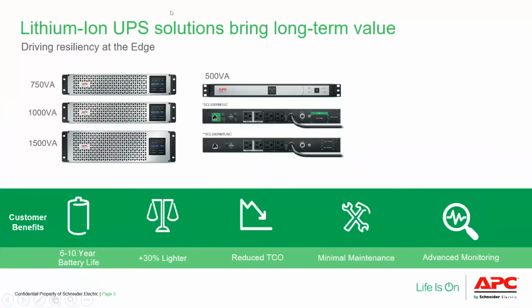From a total cost of ownership perspective, lithium-ion is a great solution for reducing total cost of ownership when paired against lead acid. You're looking at an internal battery lifespan of about 6 to 10 years, 7 to 10 in cooler environments, and also a very large decrease in weight. A 1500 VA UPS that's lead acid weighs about 63 pounds, while a 1500 VA UPS that's lithium-ion weighs about 43 pounds, so there's a very stark contrast.